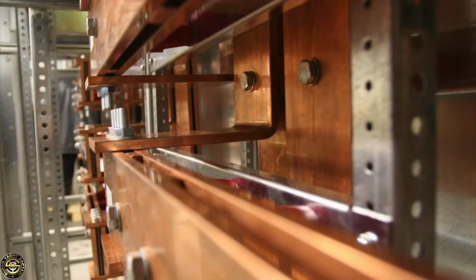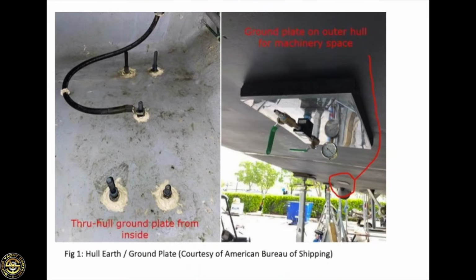However, this vessel has a GRP hull, which is not electrically conductive. So the earth in the equipment was bonded to the bus bar in the switchboard. A bus bar is essentially a strip of electrically conductive copper. And also on this vessel, the neutral part of that circuit is connected to the same bus bar. And that's the combined earth neutral distribution. The bus bar is then connected to a grounding plate that's bonded to the exterior of the vessel's hull.